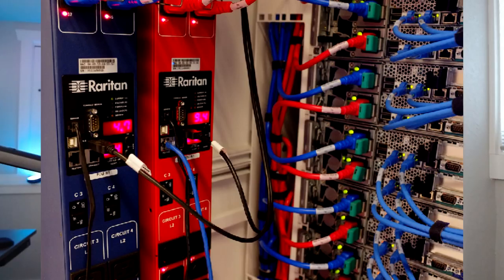Now, being a NOC tech, there are a few weaknesses that I noticed working in a few data centers. Not everything is N plus one. The few things that are not N plus one are the actual UPSs, the rack mounted UPSs, which usually sit at the very bottom of a server rack. It's just a battery bank. And the PDUs, which is another weakness where there sometimes may not be an N plus one, which is the power distribution unit. The power distribution unit is basically just a giant power strip that you plug all of the servers into.